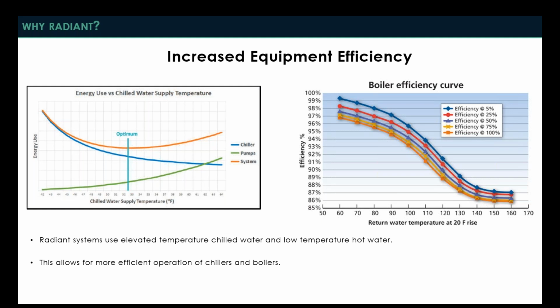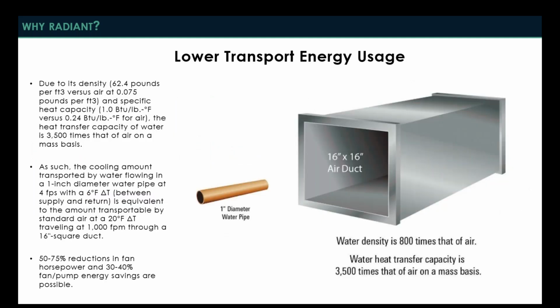So the lower temperature hot water we're making, the higher efficiency our boiler is going to have. So even a very high efficiency boiler creating, say, 120-degree water, that's going to be around 88, 90% efficient. But if you can take that down to 80 degrees, 90 degrees, now you're over 94%, 95, 96%. You're very efficient on your systems there. So that really does a lot to add to the energy efficiency of the building.